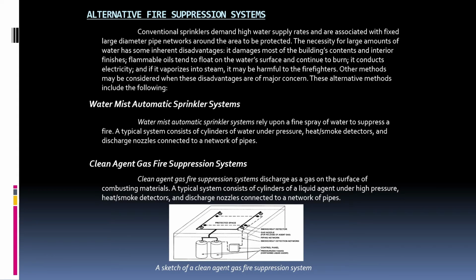When compared to conventional automatic sprinkler systems, the amount of water required in a water mist system is significantly less. Only very small amounts of water and air are needed to extinguish even the most intense fire, including gasoline fires, because a small amount of water is effectively spread into fine water droplets covering a large area.